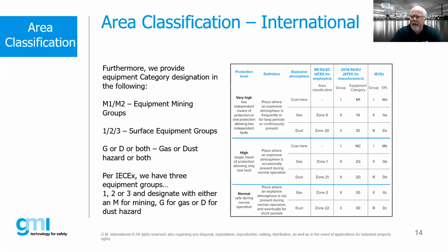And then on the far right-hand side, under the IEC Ex scheme, we have what are called EPLs. But going back to the left-hand side, for mining applications, which is something that we don't typically run into, anything below ground would be a Group 1 environment. Anything above ground, a surface industry, would be a Group 2. And then we find that we have surface equipment groups under the ATEX directive 1, 2, and 3.